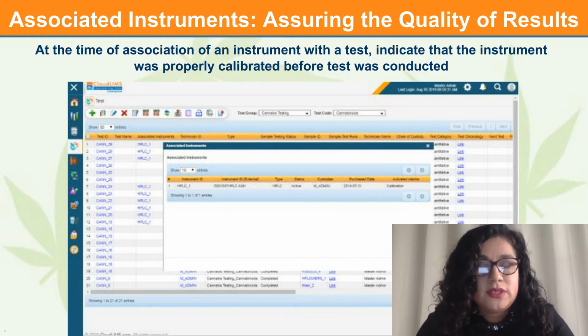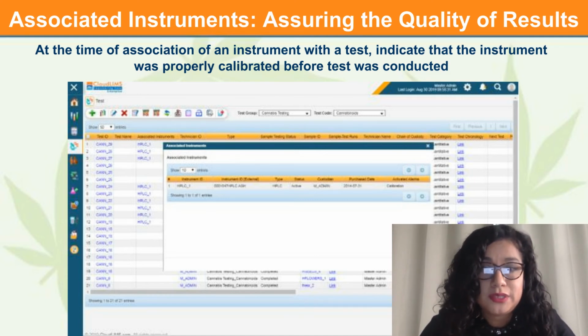Traceability is essential for 17025 compliance in a third-party testing lab, and it is really useful in an in-house testing lab as well. If someone asks how we know that the test result you provided was performed on an instrument that was properly maintained and calibrated, the LIMS will show that traceability. When was the test done, when was the previous calibration done, and of course, which SOP was followed for that calibration, most recently. So you have a fully traceable record showing that your instrument was calibrated and maintained when you ran that sample.